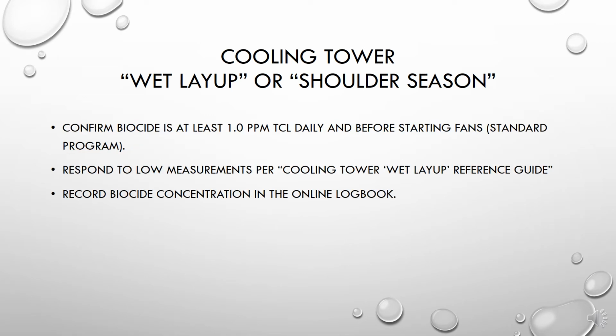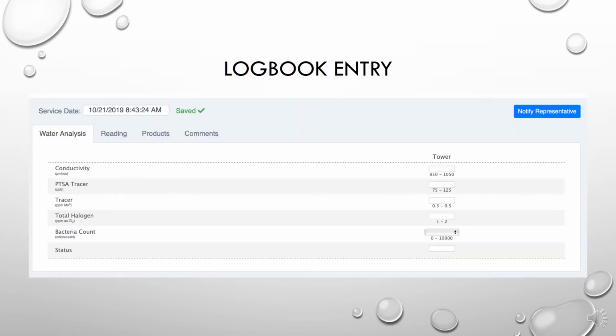So, this daily circulation, we want to confirm biocide is at least 1 part per million every day. This is our standard program. Respond to low measurements per that wet layup reference guide, and we want to record that biocide concentration daily in our online logbook, just like last year. So this is that logbook entry. As a reminder, something new that we added last fall was this Notify Representative link. When you click that, it will open up a comment box for you to send any questions or comments to Eldon Water. It also goes to select individuals on the water safety team.